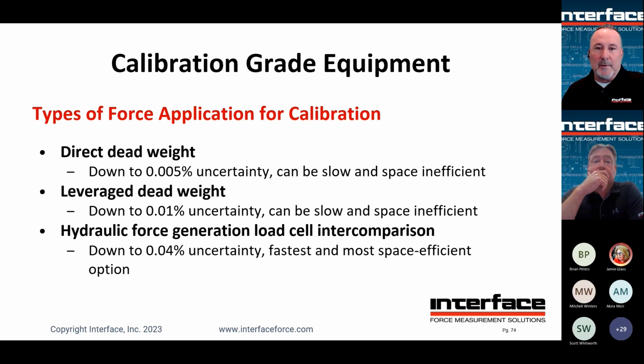Leverage dead weights would be a system with a dead weight stack that you may apply manually, picking them up and putting them on a platen to apply loads to your load cell, or perhaps through a lever arm to measure torque that way. Again, very low uncertainty levels, but these can be slow methods for applying load.